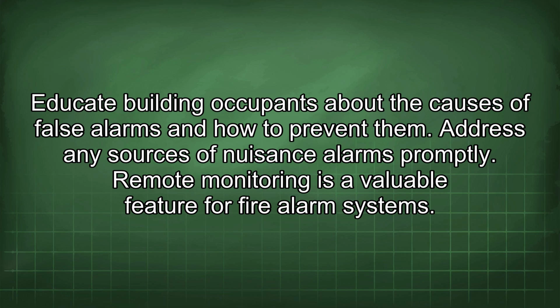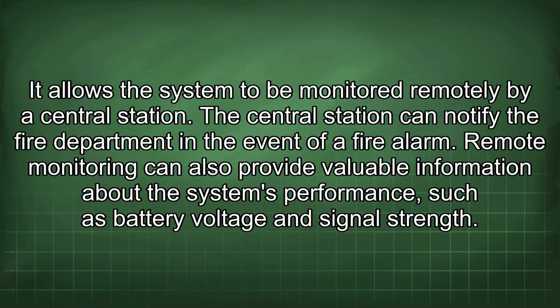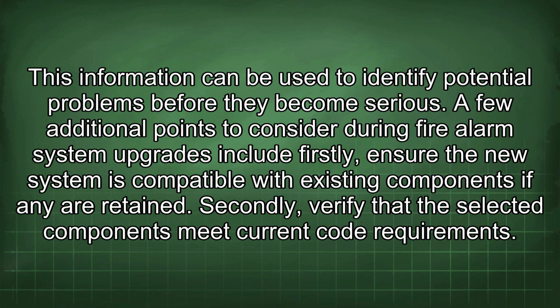Remote monitoring is a valuable feature for fire alarm systems. It allows the system to be monitored remotely by a central station. The central station can notify the fire department in the event of a fire alarm. Remote monitoring can also provide valuable information about the system's performance, such as battery voltage and signal strength. This information can be used to identify potential problems before they become serious.